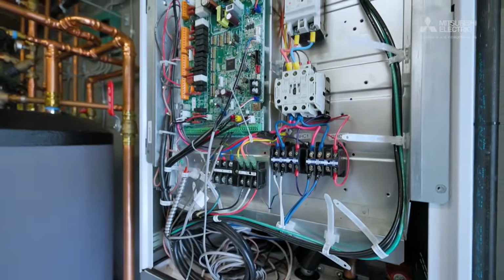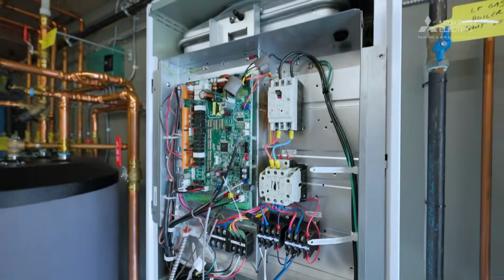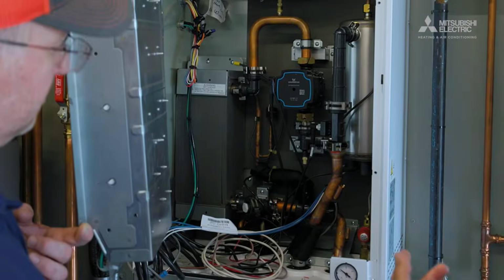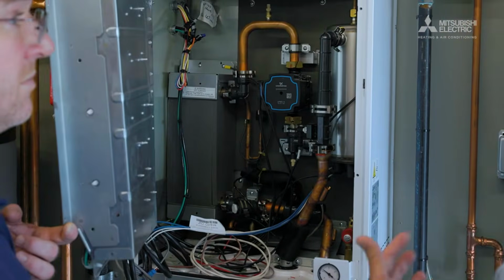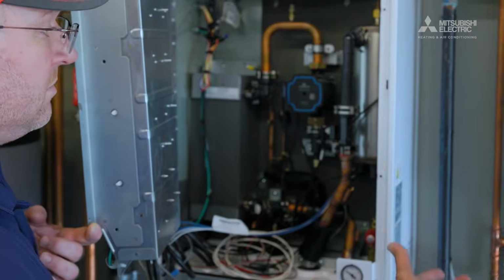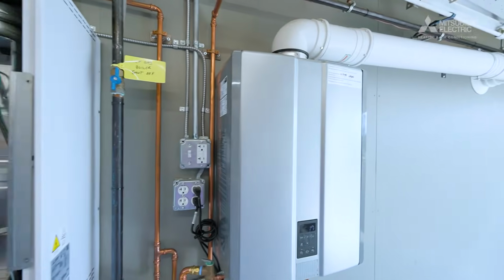The Hydro Box has all the components built in. It's got the control board, the water pump, the expansion vessel, a plate heat exchanger, a magnetic filter, all these devices that are basically running in tune with each other. Most importantly, we're using a variable speed pump, which allows us to really optimize the system usage, optimize the energy efficiency of the system. But what we're doing is packaging all of that in a solution that talks with the outdoor unit directly.